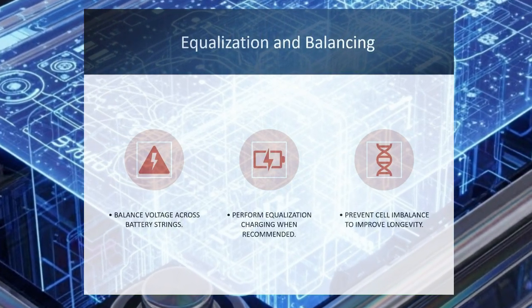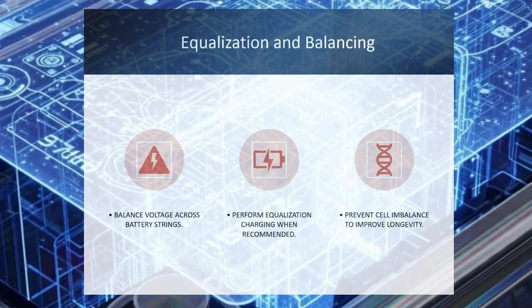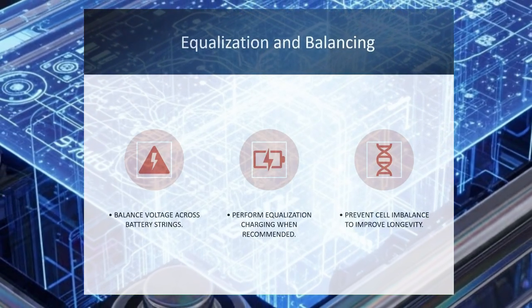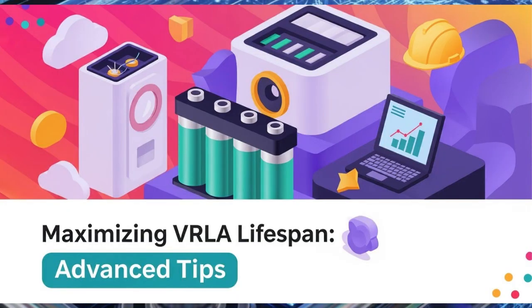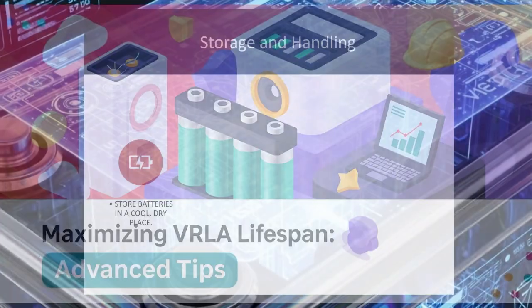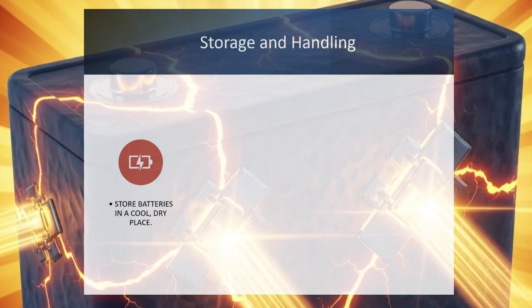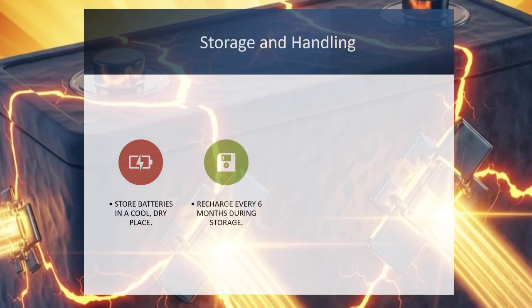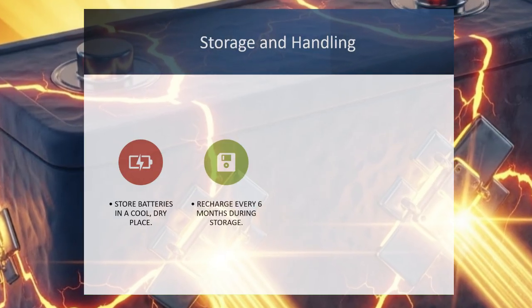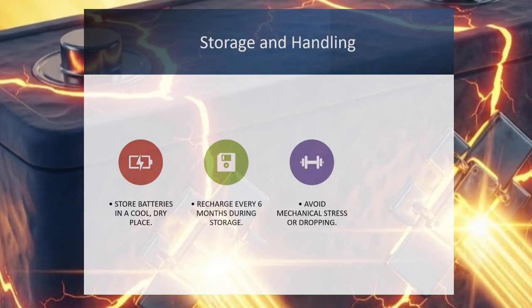Storage and handling. When storing VRLA batteries, always keep them in a cool, dry place. Even during storage, they must be recharged every 6 months to avoid sulfation. Batteries should never be dropped or exposed to mechanical stress. And when handling them, always use insulated tools for safety.